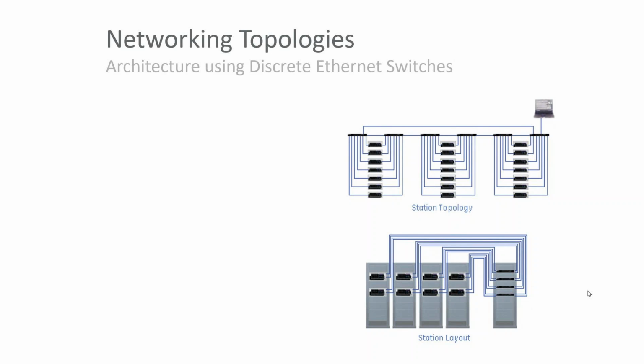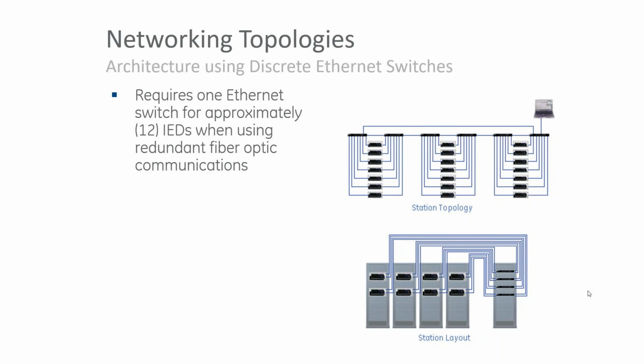So these are some topologies we could use within our environment. For example, in this substation topology, we could do it two ways: we could have Ethernet switches on each lineup, with devices connecting to those switches, which then go back to our central location or server. Or we could have switches on one panel instead of segregated by switchgear lineup, with a dedicated communication panel where everything goes back to that panel.